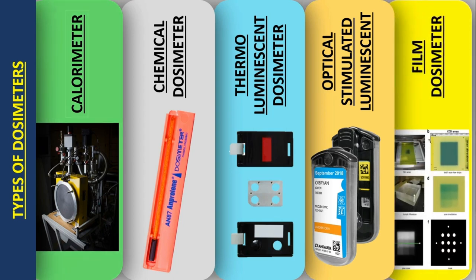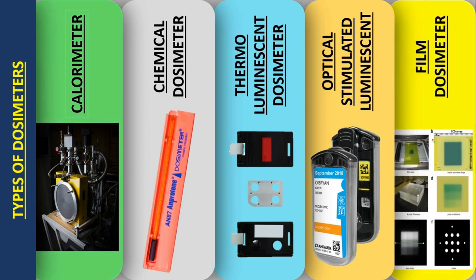Finally, we have the film dosimeter. Radiochromic film consists of a single or double layer of radiation-sensitive microcrystals on a thin polyester base. The color of the film becomes dark when exposed to radiation, and the darkness of the film increases with an increase in absorbed dose.